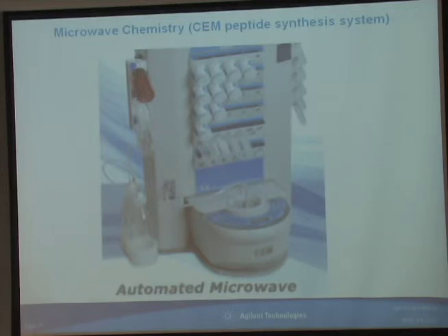The problem with this right now is that you have to try different times of microwaves for each reaction to figure out the protocol of what you're really going to do. It's an open loop instrument. So what we're proposing is to put a network analyzer at an offset frequency in there to actually see what's going on. Now the problem is this is like a $20,000 instrument, and our network analyzers are typically that much or more, so it doesn't really fit this market yet.